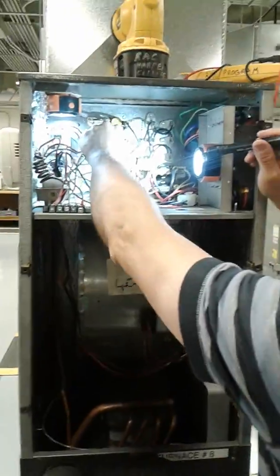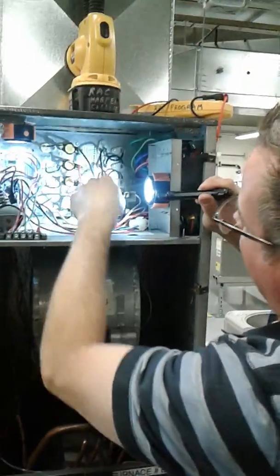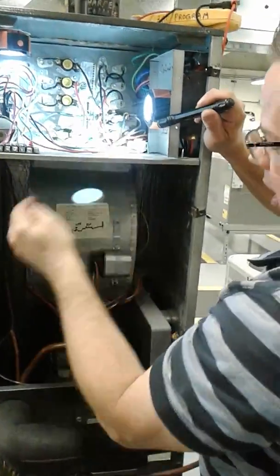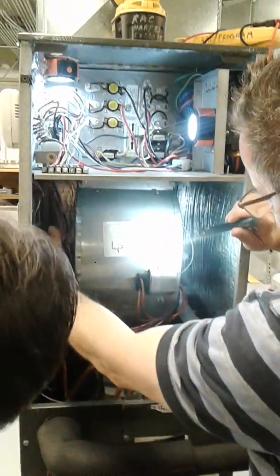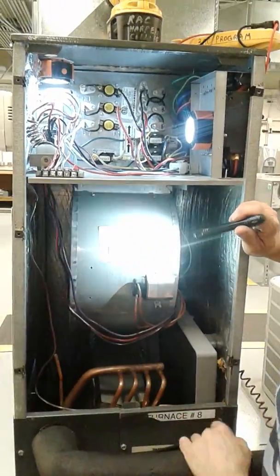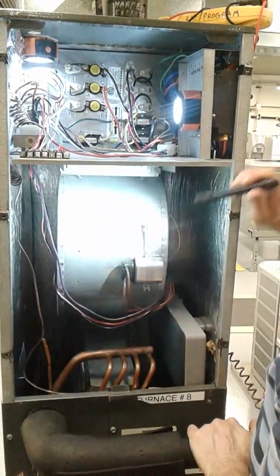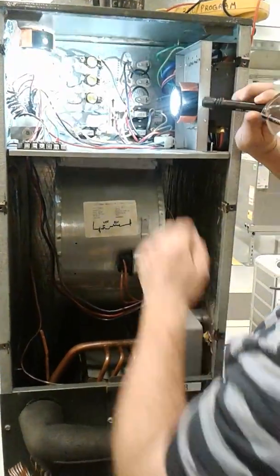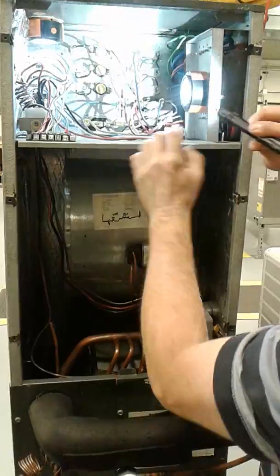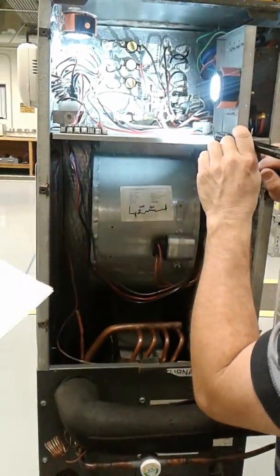Yes, there's other things you need to check. You need to check your connections, make sure they're nice and tight. Make sure you have no burnt wires. Okay. Make sure the blower wheel's actually clean. Okay. That you can take out and clean as well, like you do. Okay. Yeah. Big thing is you want to check all your connections on your wires. That's the biggest thing right there.